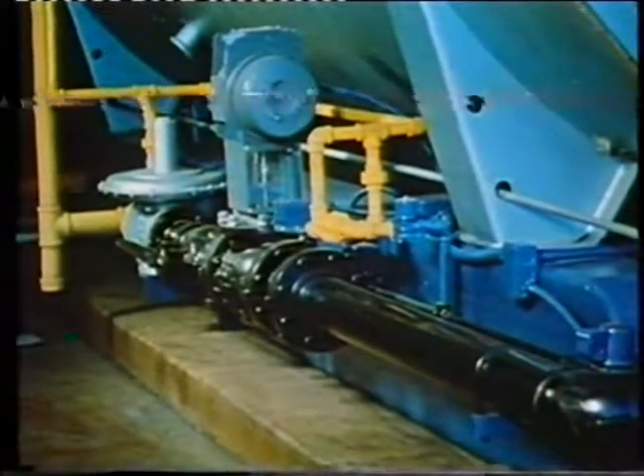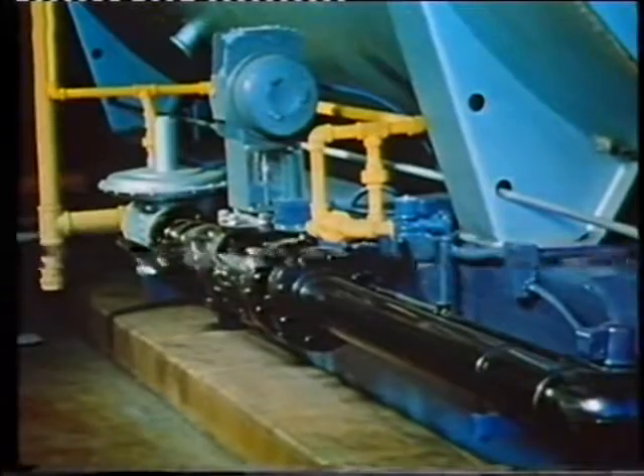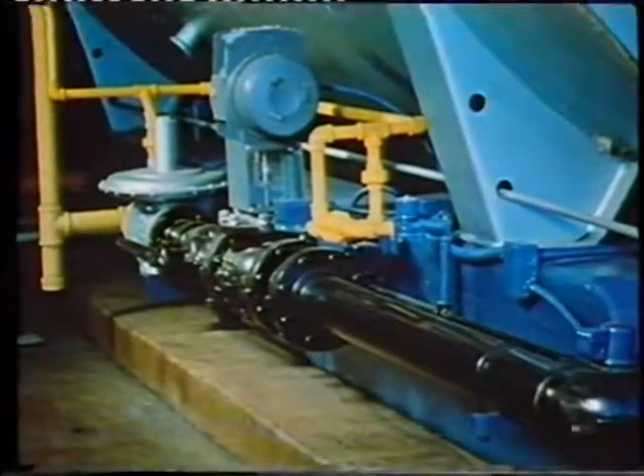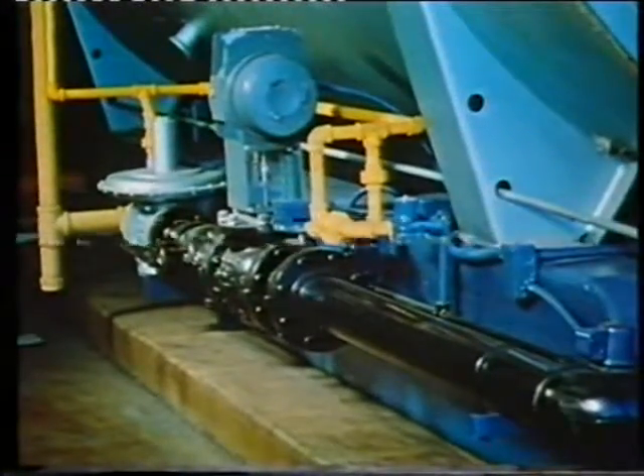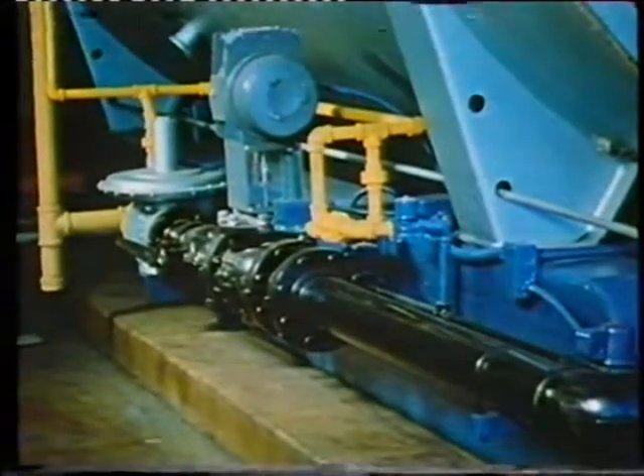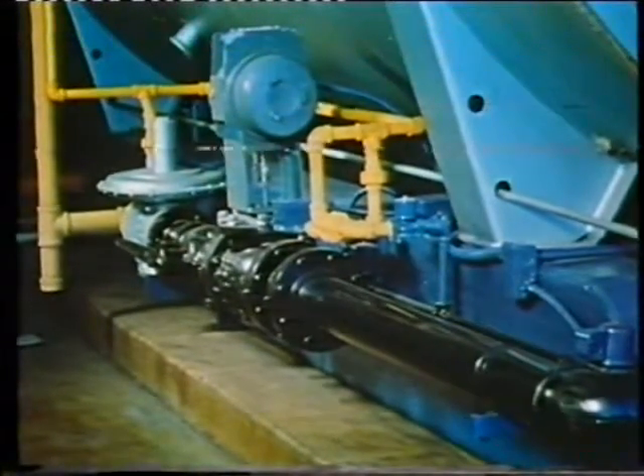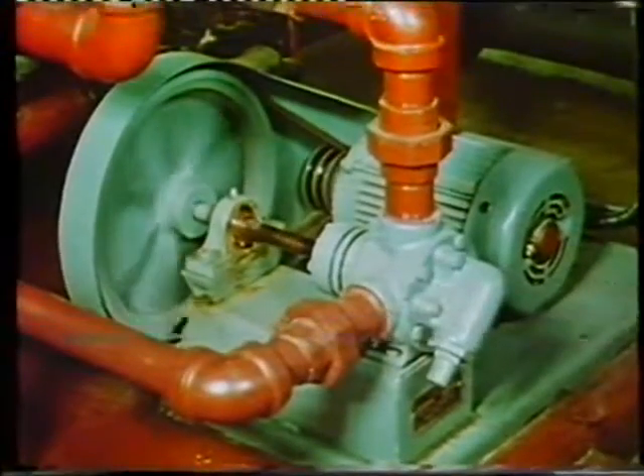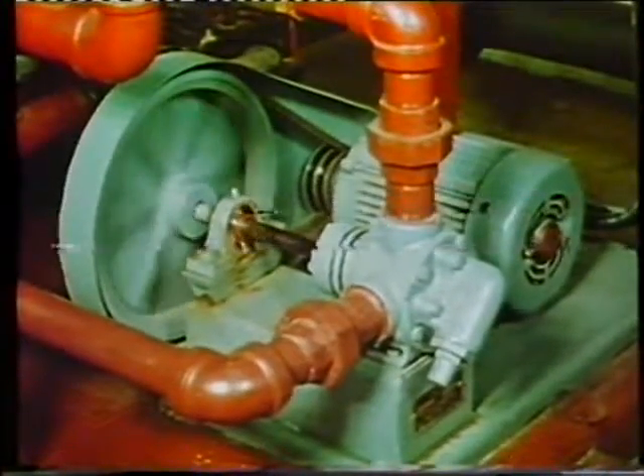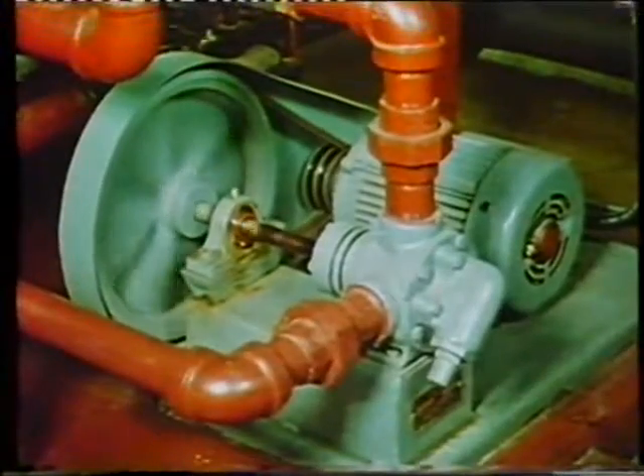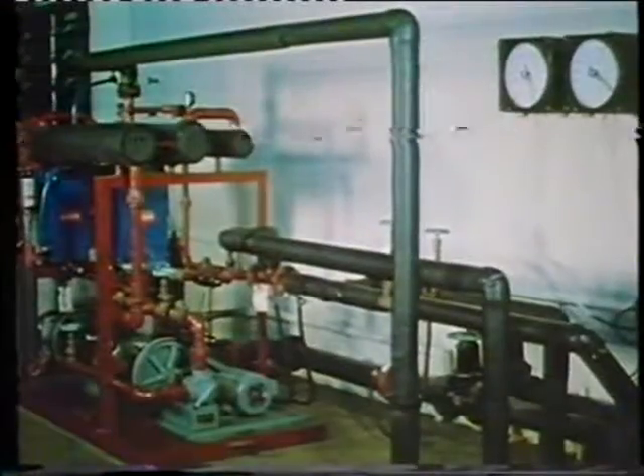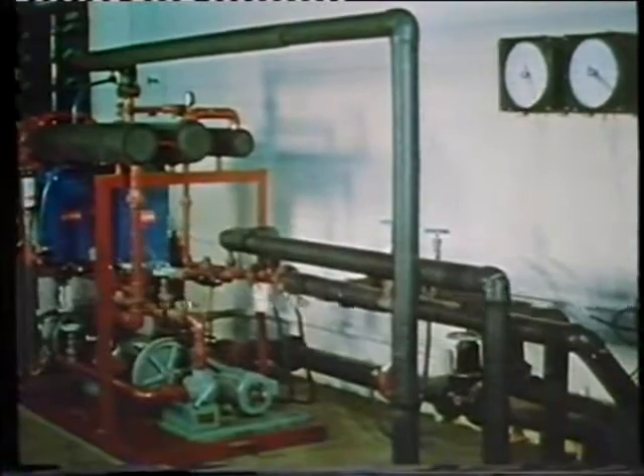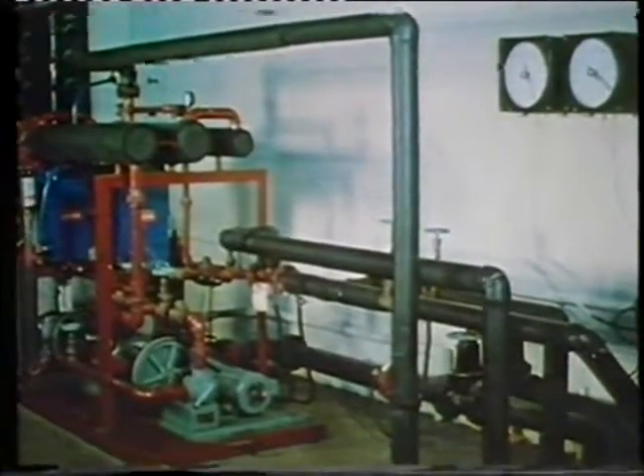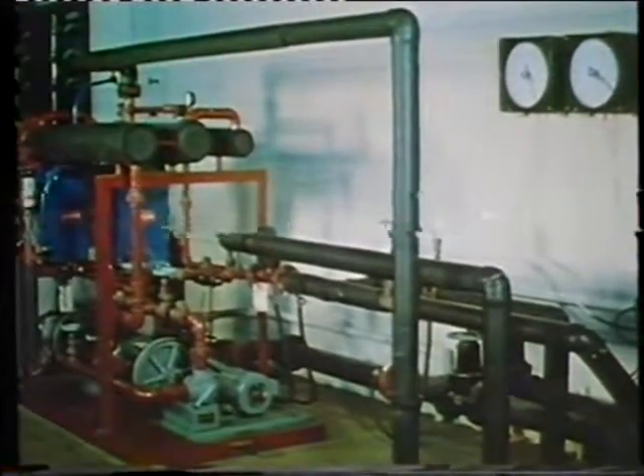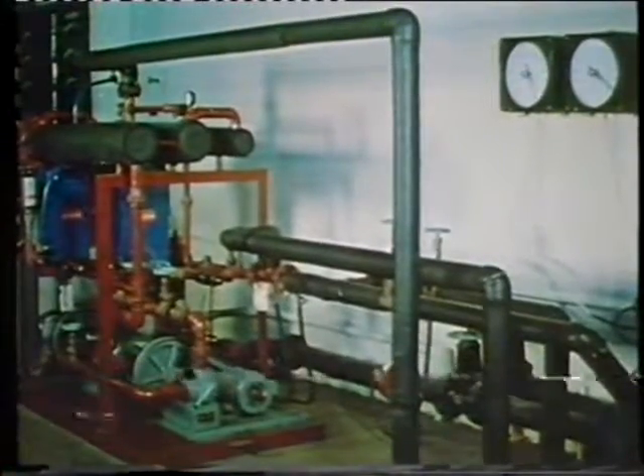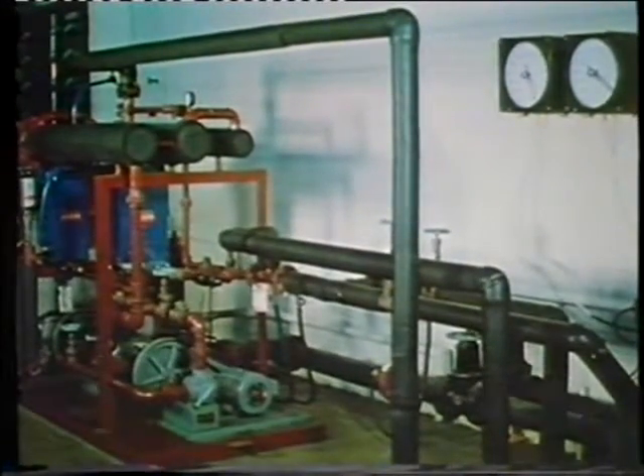The basic boiler fuels, gas, oil, or coal, require different feed systems and combustion techniques. Fuel oil requires atomization. Natural gas does not. A typical oil feed system utilizes pumps, strainers, heaters, and pressure relief valves. Oil is drawn from the storage tank through strainers and is pumped to the heaters. A check valve, shutoff valve, and other control devices may be utilized at the oil storage area.